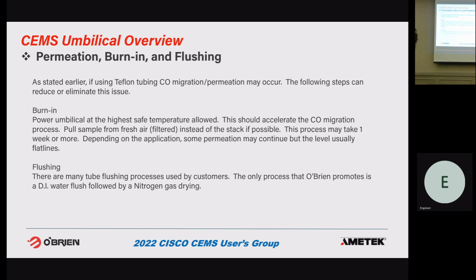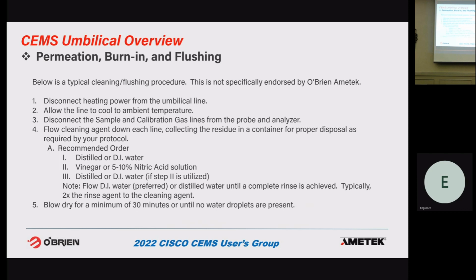Permeation. So with Teflon, as I said earlier, there can be permeation issues. This is some of the burn-in feedback we've gotten over the years, compiled mainly from our customers. We generally recommend just doing a DI water flush, even though lots of customers use different solvents, which probably work better. We haven't tested that, so we can't say. Plus there's always the danger with solvents if the person didn't disconnect power from the tracer, you could get an arc. So while solvent flushes work, our recommendation is a DI water flush, then a nitrogen gas purge until all the moisture is out.